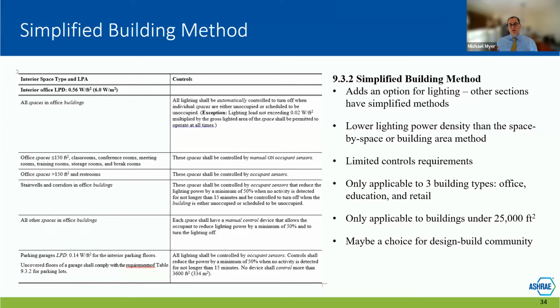You are going to get a lower power density than either the space-by-space method or the building area method, and the reason is you'll also have fewer control requirements. So the idea is this is meant to be simplified, for a pretty easy standalone building where you're going to use only a certain amount of power, primarily a lot of occupancy sensors in a lot of the spaces. The trade-off makes it a more efficient building because you're using a little less power and you don't have to use as many controls. That's the idea of that simplified term.